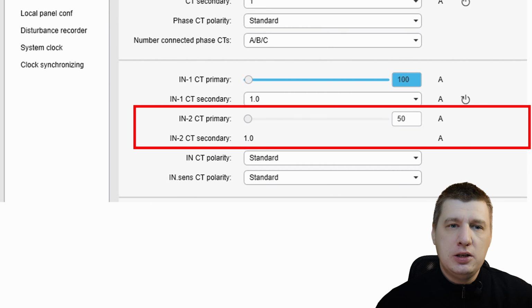In high impedance or isolated networks, a ground fault might only leak a few amps. A 50 amp primary CT allows the relay to see those tiny changes with extreme accuracy. Core balance CTs like the CS series often use this lower primary rating to provide a very high transformation ratio.